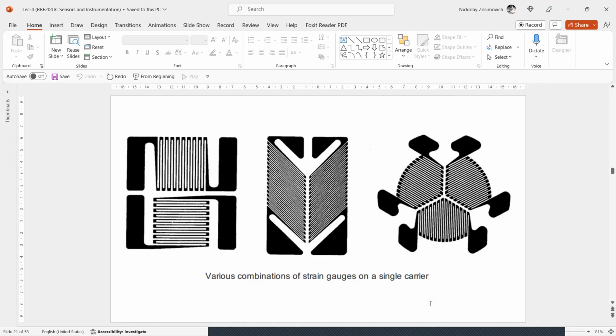A condition for adequate temperature compensation is proper mounting of the 2 or 4 active bridge elements. The combined gauges in this figure are very useful, since they guarantee optimal temperature matching. Strain gauges in a differential bridge configuration allow the measurement of very small strain values, down to 0.1 microstrain. The problem of measuring such small strain is actually shifted to the bridge amplifier. Its offset, drift, and low-frequency noise obscure the measurement signal.